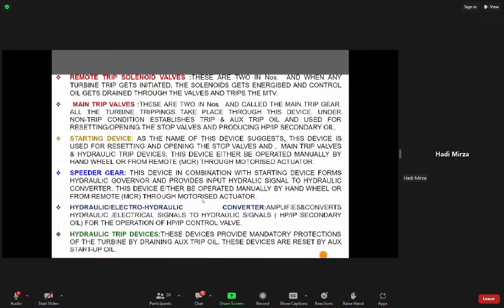Hydraulic and electro-hydraulic converters and its amplifier convert hydraulic and electrical signals to hydraulic signals. Basically, after trip oil is generated, it comes to the electro-hydraulic and hydraulic converters. These are two devices separately, with a follow-up piston in each device. The function of the hydraulic converter is to convert trip oil into the required secondary oil pressure for control valve opening.